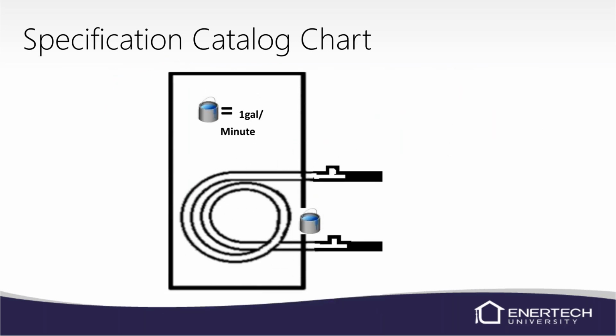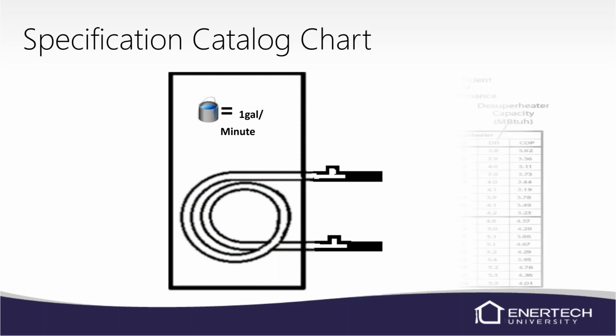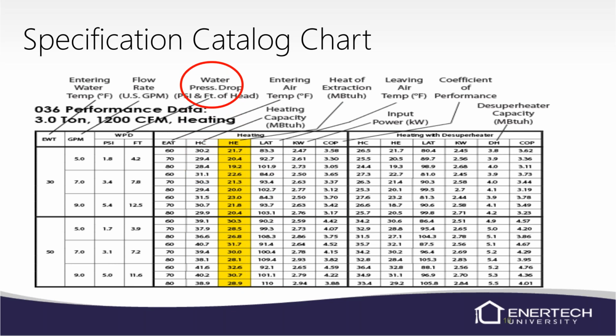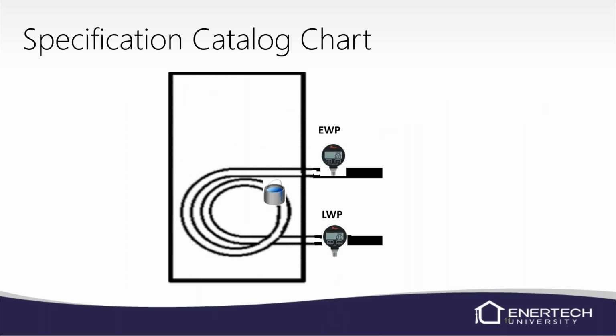So again, flow rate is normally calculated in gallons per minute. Normally on a closed loop system, we look for 3 GPM per ton. So 3 gallons per minute per ton. So a 3-ton unit, full load, you would want 9 GPM. On an open loop, we can go down to about 1.5 GPM because we have a more consistent water temperature, about 50 degrees. So PSI pressure drop, that's what we're going to ask you when you call in to tech support. We're going to take your pressure gauge, take your pressure in, and take your pressure out, and do the math, and that's going to give you your pressure drop.